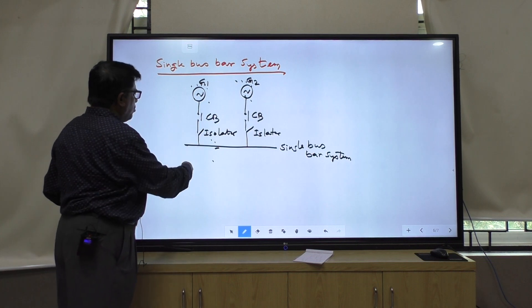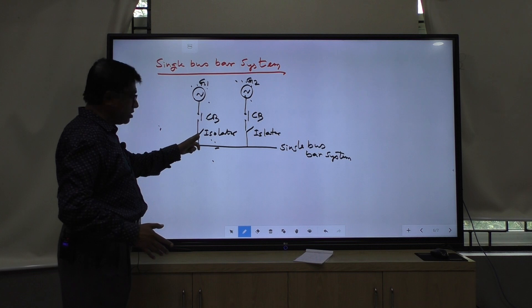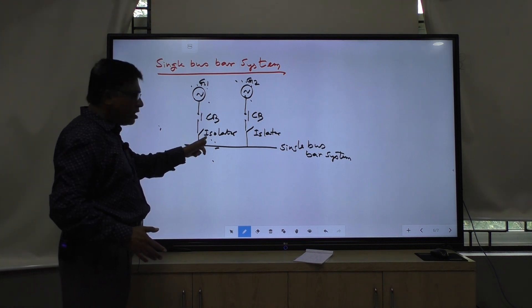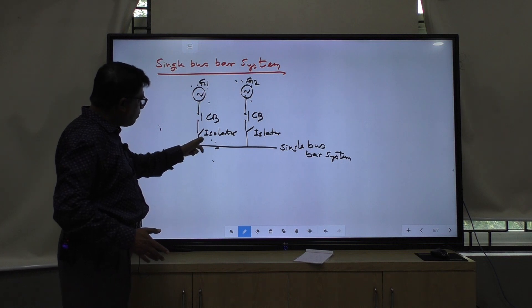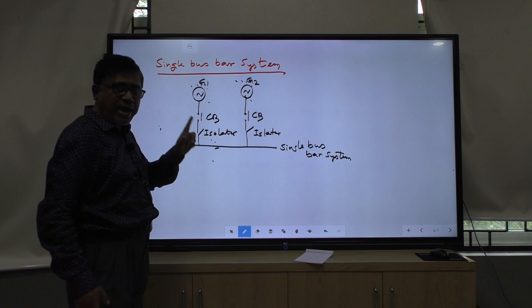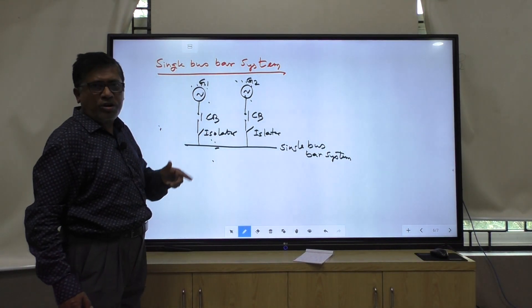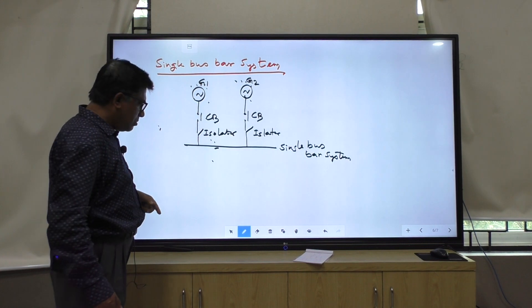It is just manually controlled. Open or close. No load condition. Very important thing I am discussing. Isolator should operate at no load condition. But breaker can operate at load condition or at no load condition.